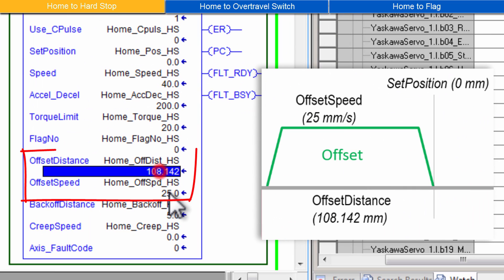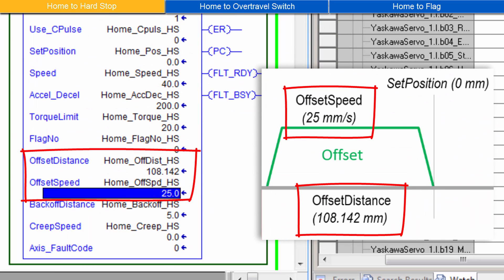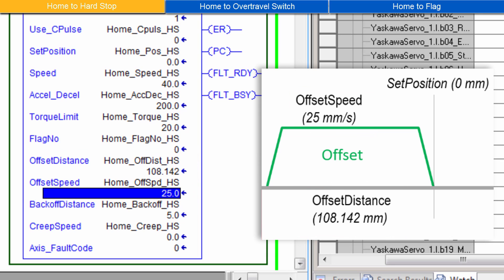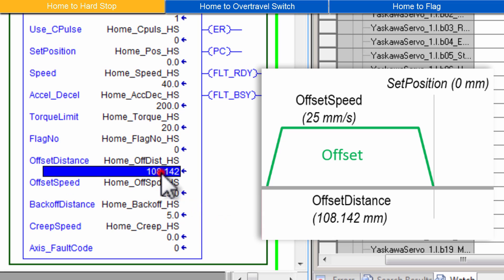Offset Distance and Offset Speed define the final offset move after detection of the Hard Stop. I have an Offset Speed of 25mm per second. And I have experimentally determined that 108.142mm is the correctly calibrated Offset Distance.